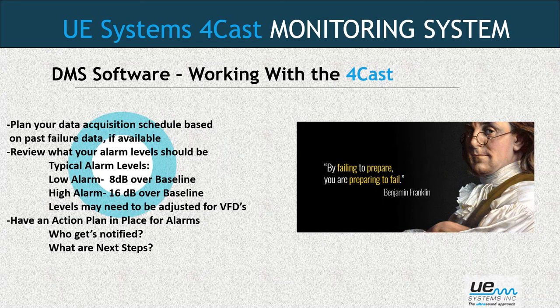Review what your alarm level should be. Typical alarm levels we use, 8 decibel rise over a baseline. That's our low alarm level. And most of the time that indicates the friction level's gone up, but damage hasn't actually been done to the bearing yet. What we need to do is probably lubricate, and that should bring it down to baseline. Our high alarm is double that, 16 decibels over baseline. And the high alarm in the majority of cases is going to tell us that we're past where lubrication is going to bring it back. We've actually got some type of a fault that's developed, and we're into a failure mode now on that bearing.